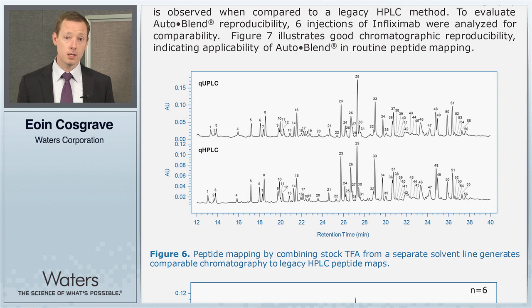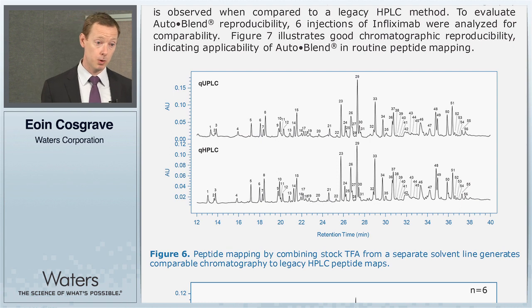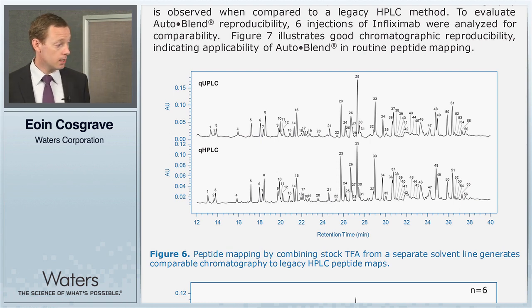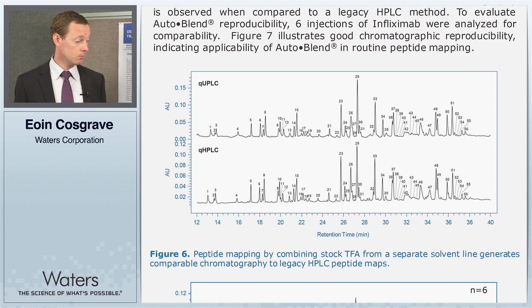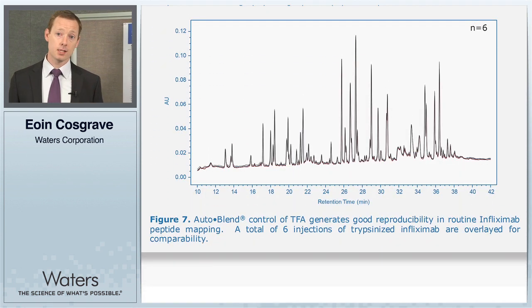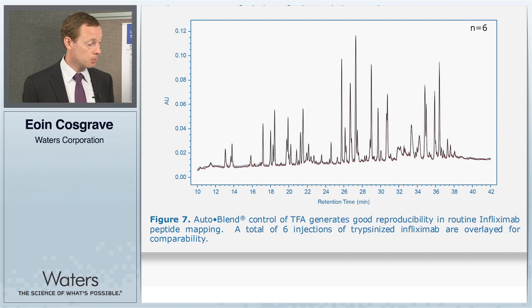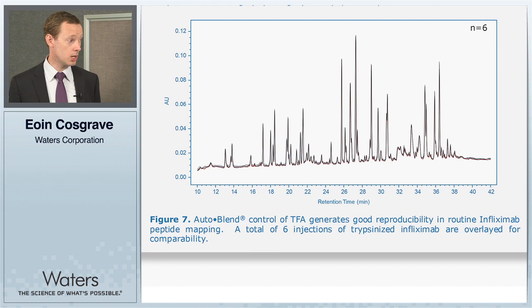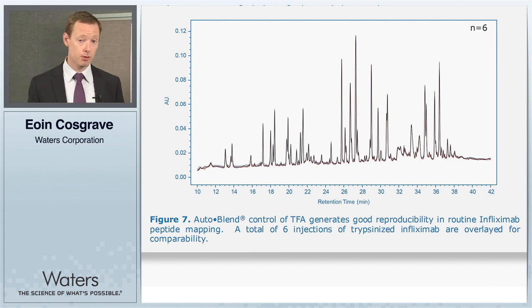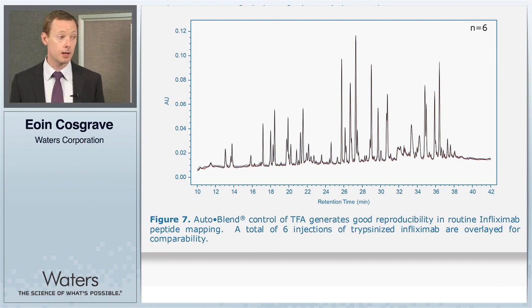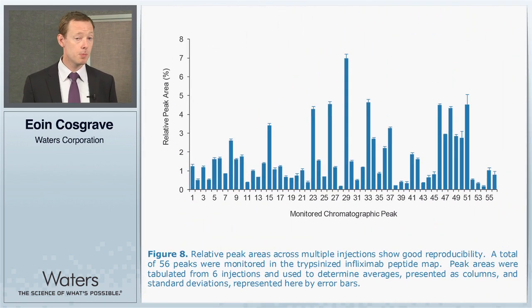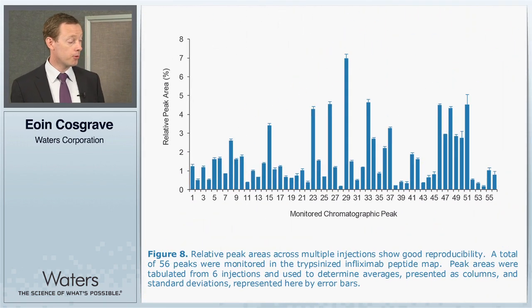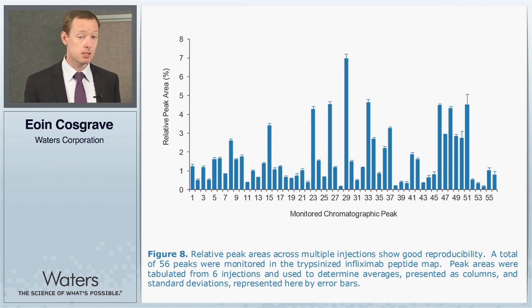The real goal was to assess reproducibility using AutoBlend, since that is the big challenge for QC labs. In figure seven, we overlay six different injections and find it's indistinguishable — there is no difference between these chromatograms, which is exactly what we hoped to achieve. In figure eight, we looked at the reproducibility of peak area across six injections using AutoBlend, and the peak area reproducibility is excellent.